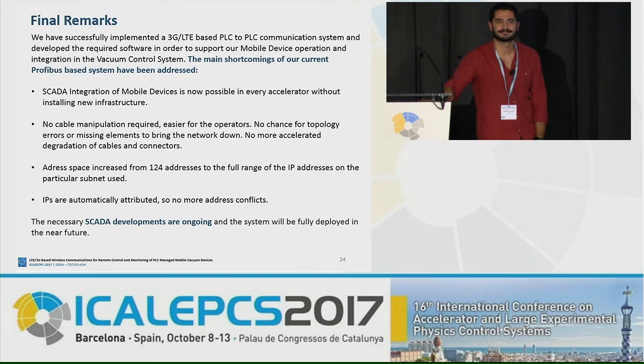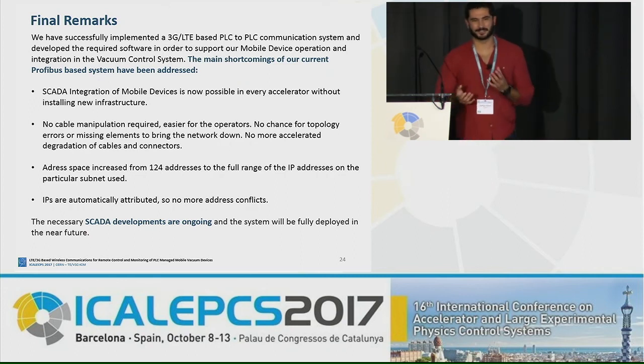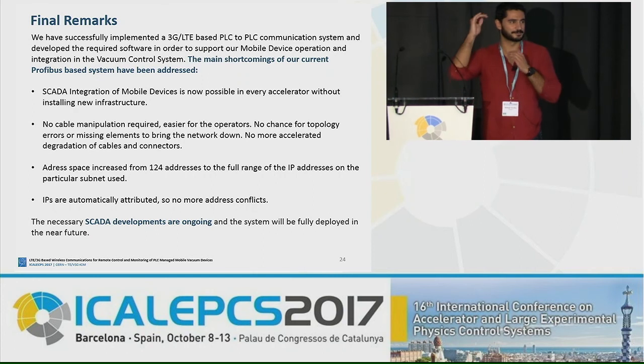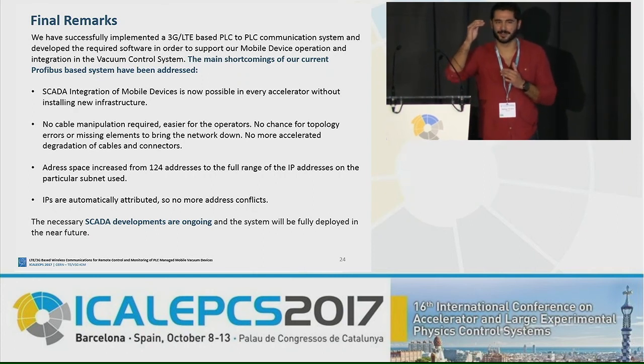Question: What about the communication speed — is it much faster than the original Profibus solution? Answer: It doesn't make much difference, because what we're exchanging is the state of a pumping group — about 48 bytes, exchanged every 2 seconds. But if in future you plan to connect directly to the SCADA, it would be faster.